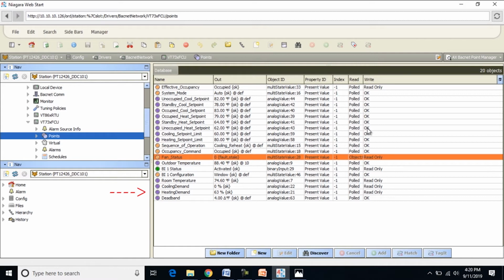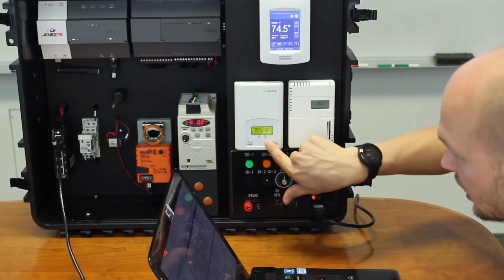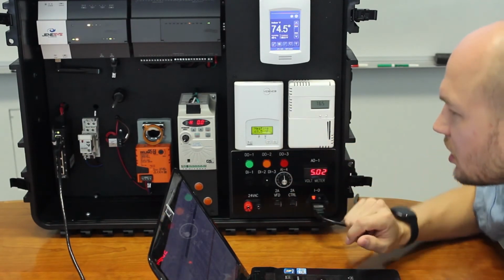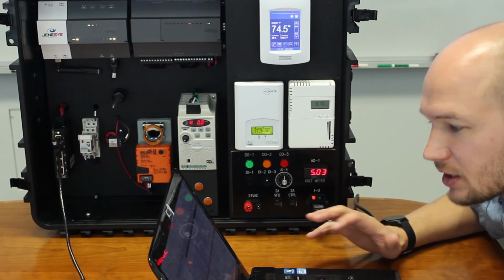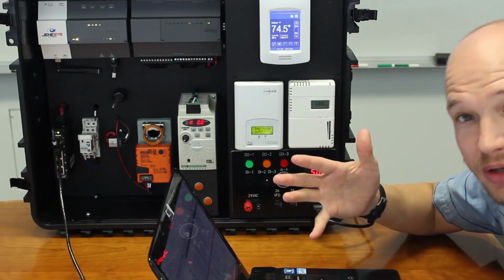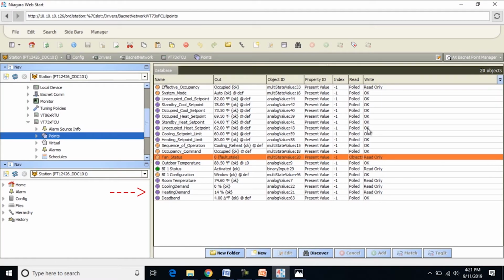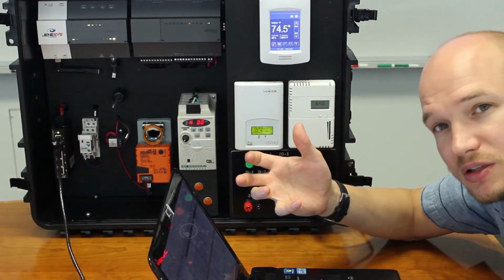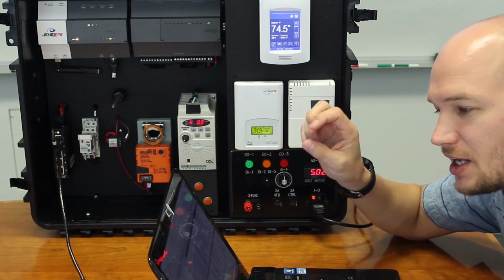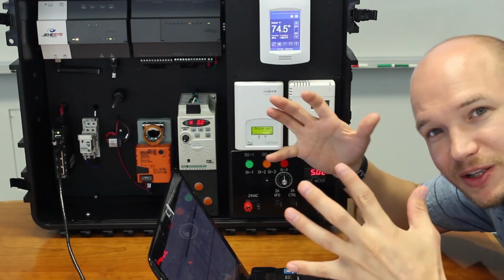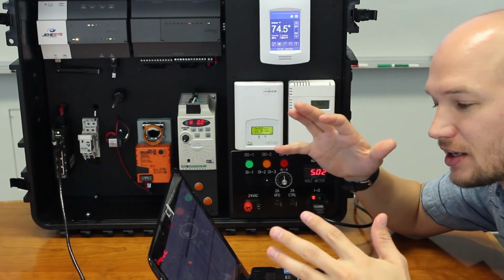So there you can see it's 63%, and it may stay there for a little bit, and as we got closer and closer to our set point, it would continue to drop, 14%, and so forth. And so likewise, if we brought this temperature down, we're going to see the cooling switch over, and we'll see some of the changes that display on the computer. So you can see the swap over, heating went to 0, cooling went to 37%. Now it would run until it started to cool the room, would get feedback from the thermostat or the set points or the room temperatures, and it would use its algorithm, its smart controller brain, and change that demand for cooling.